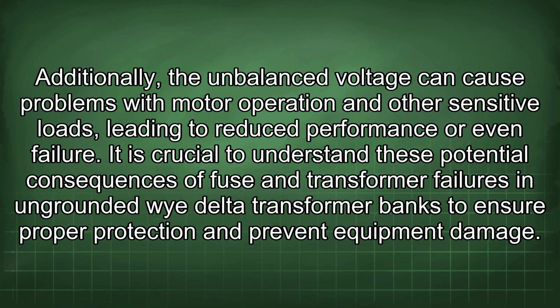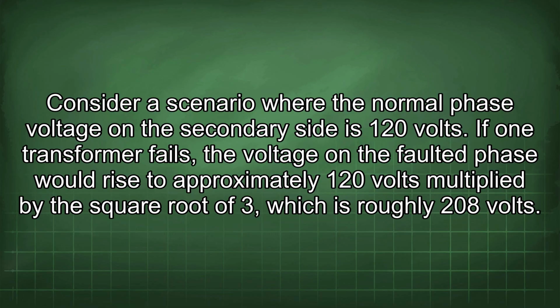Additionally, the unbalanced voltage can cause problems with motor operation and other sensitive loads, leading to reduced performance or even failure. It is crucial to understand these potential consequences of fuse and transformer failures in ungrounded Wye delta transformer banks to ensure proper protection and prevent equipment damage. Consider a scenario where the normal phase voltage on the secondary side is 120 volts. If one transformer fails, the voltage on the faulted phase would rise to approximately 120 volts multiplied by the square root of 3, which is roughly 208 volts.